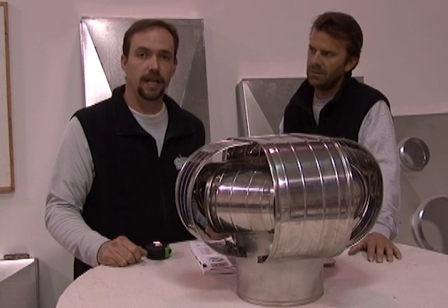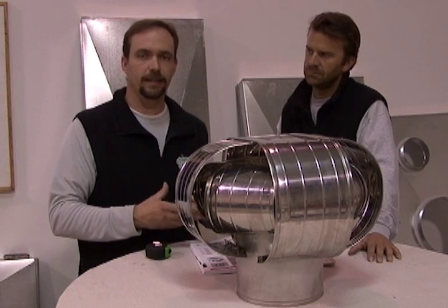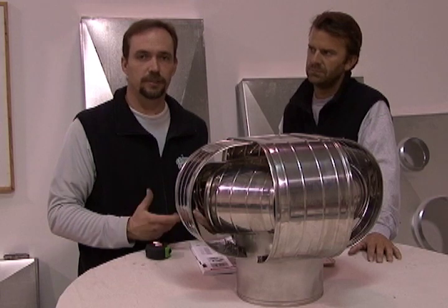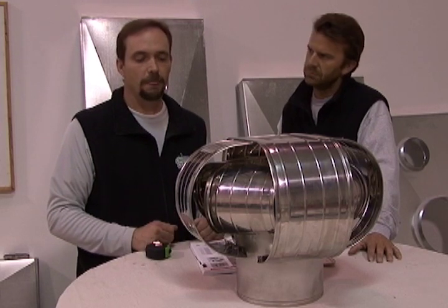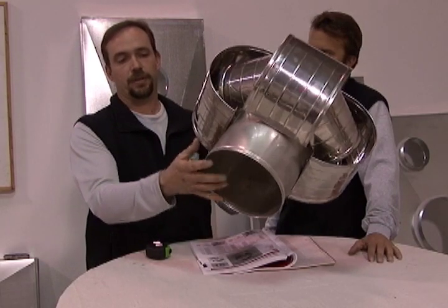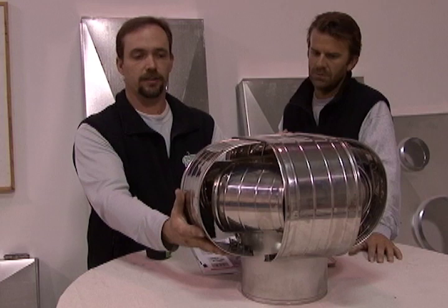The second application you're going to have is for a Class A chimney, or a solid pack insulation chimney for like a wood stove, a freestanding wood stove. Obviously, you don't need any adapter. You measure the diameter and this is going to slide right down inside the factory built Class A chimney system.